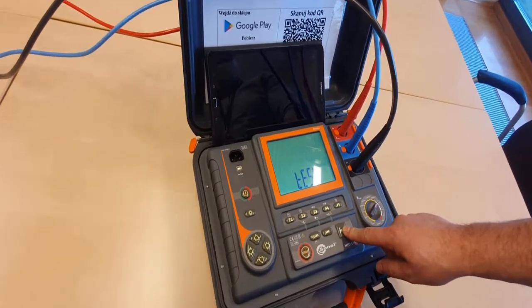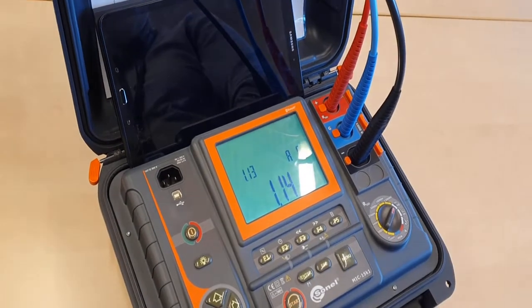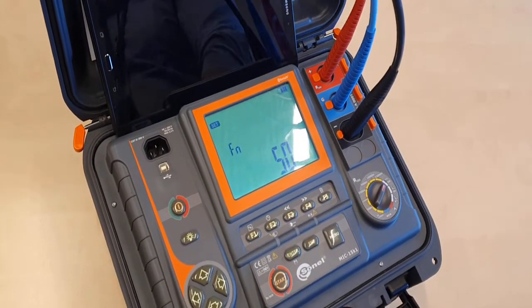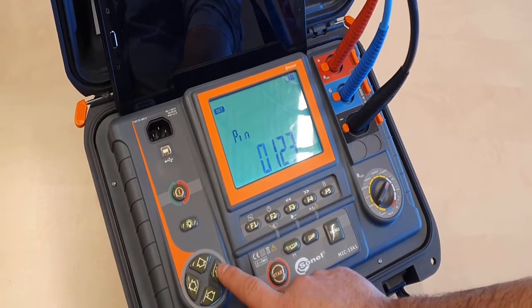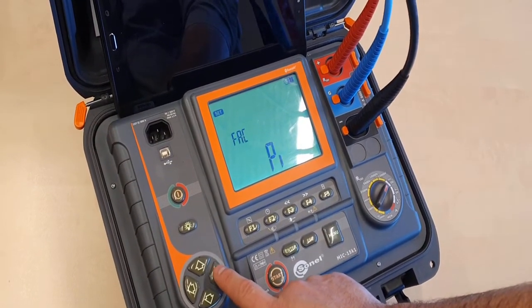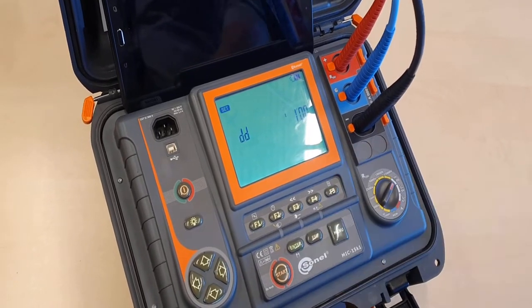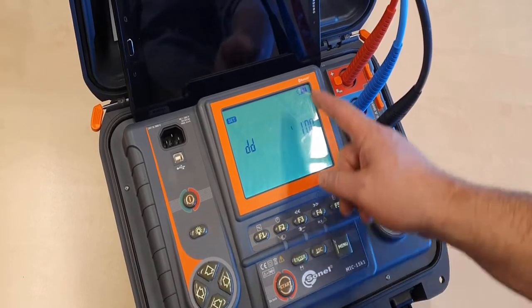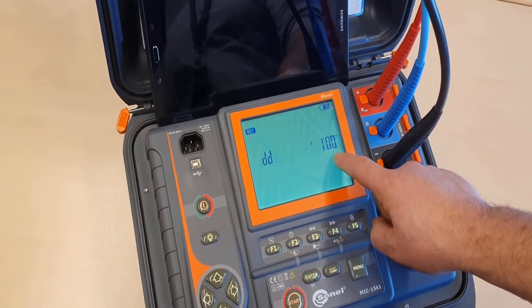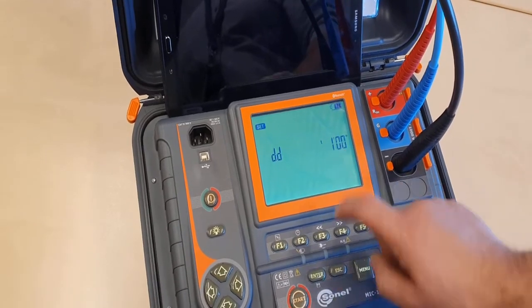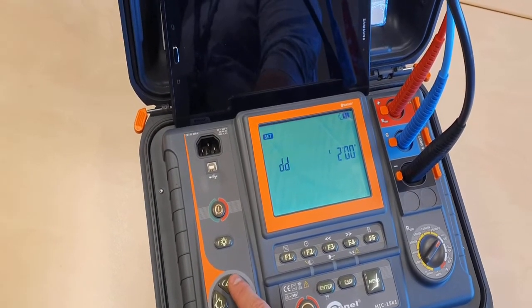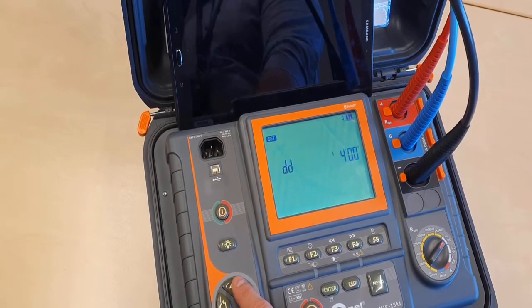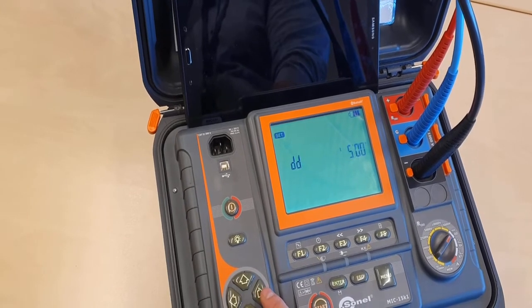Using arrows, we have to go to select the DD measurement time. As a standard for DD measurement is set to 1 minute. For PDC measurement, a longer time will be much better. I set 5 minutes only not to make the video too long.